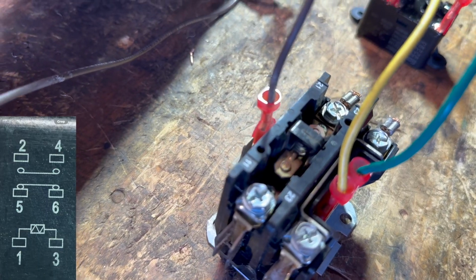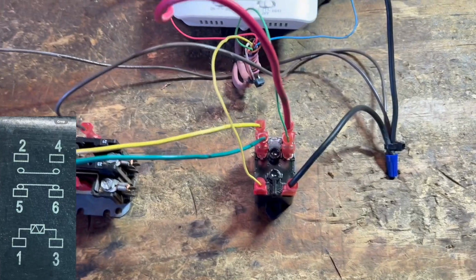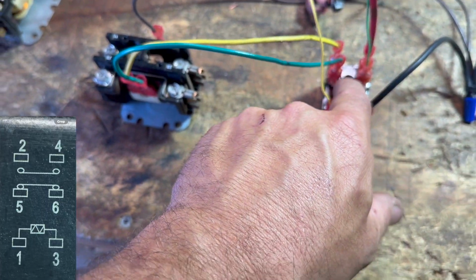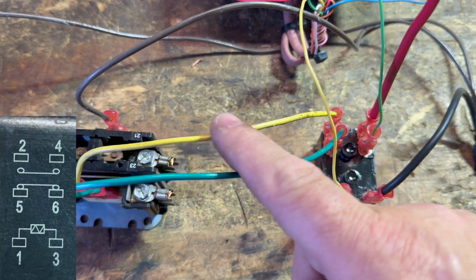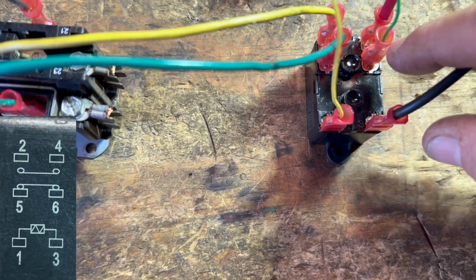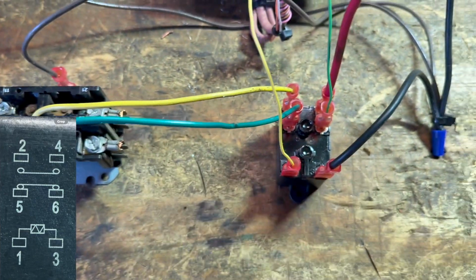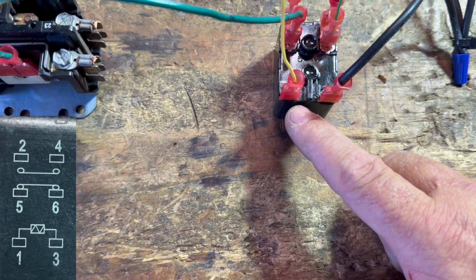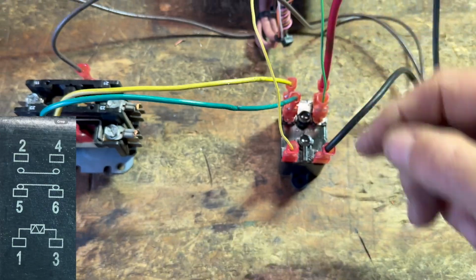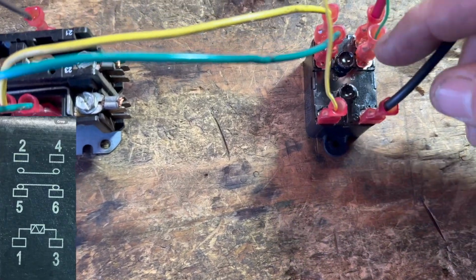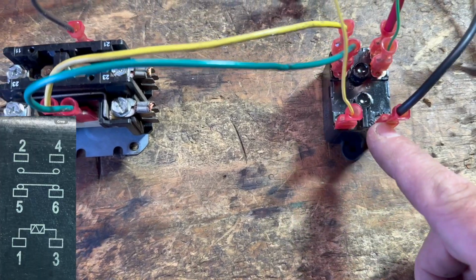And we'll go ahead and turn them off, and I'll turn the thermostat off from cooling, and you can see the load release itself. This would disconnect high voltage. There you go. So that's what a relay does. Again, the key things to remember between 2 and 4, kind of hard to see, but that's that yellow and that red in the back. We have positive 24 volts coming in, going to our external load. Here between 5 and 6, we've got just the control, whatever we want to activate this load with normally. And between 1 and 3, we've got a command control to tell it when to turn on 2 and 4. So 1 and 3 turn on 2 and 4. 5 and 6 are just normally closed, but they open up when 1 and 3 are activated.